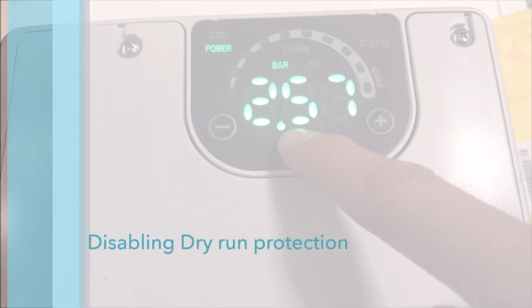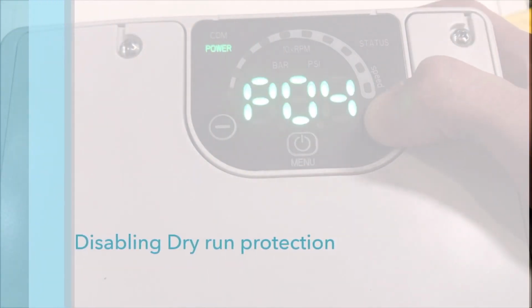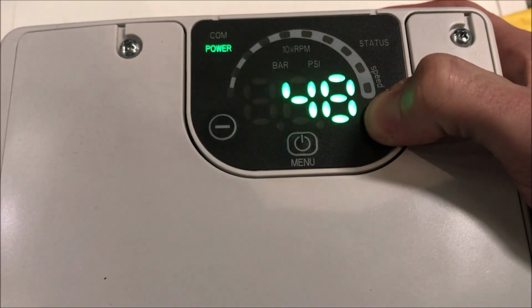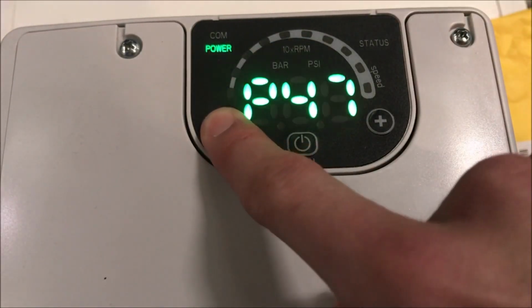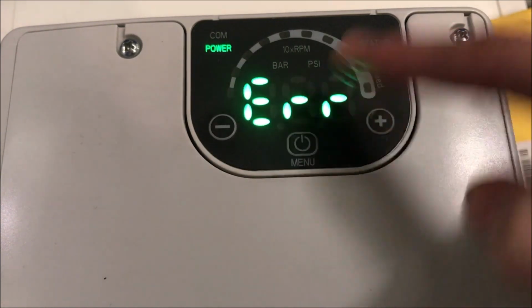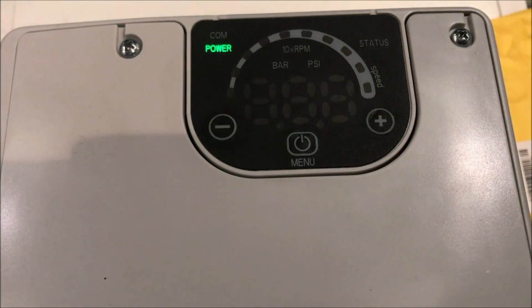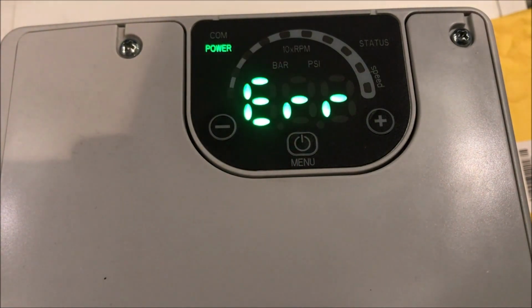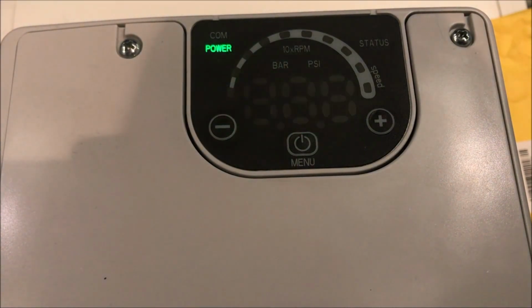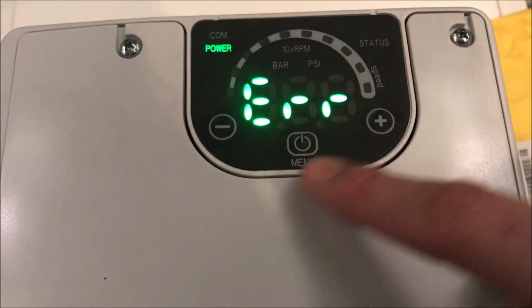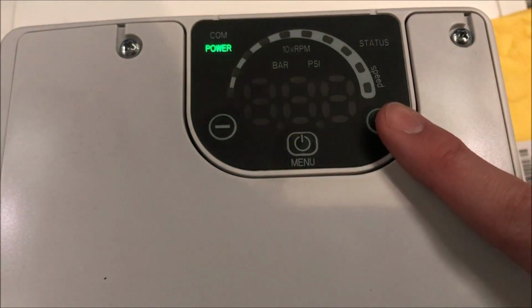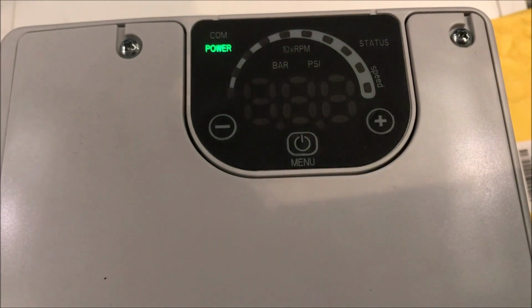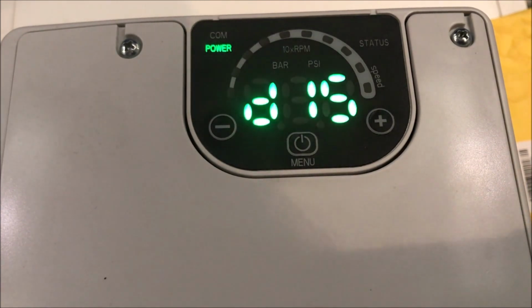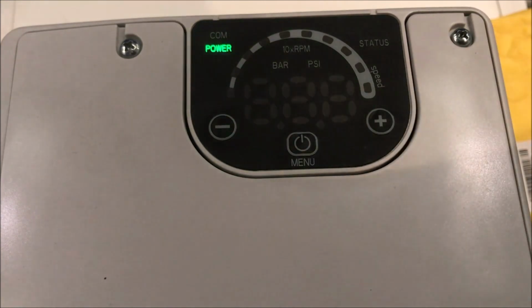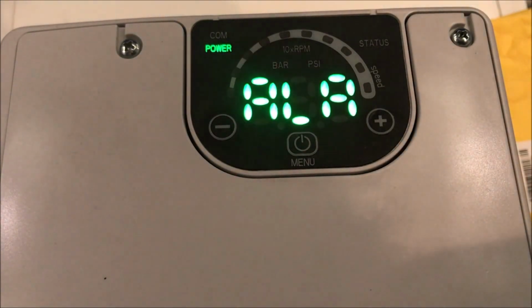You can change how the pump reacts when a lack of water is detected in parameter 48. Options available include putting the pump into error mode, preventing the unit from running. This is the default setting, protecting the pump from dry running. Disabling the pump from reacting when detecting a lack of water. And alarm, where the error code and status warns of dry running, but the pump continues to run.